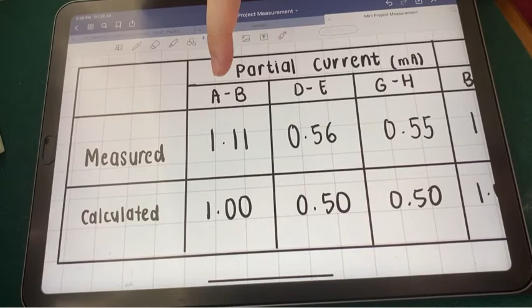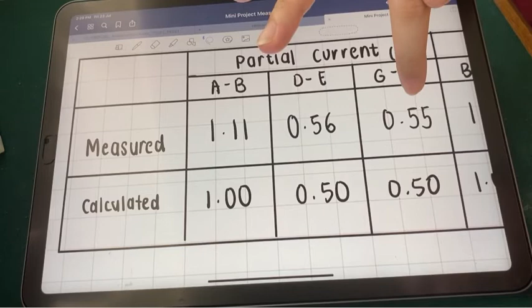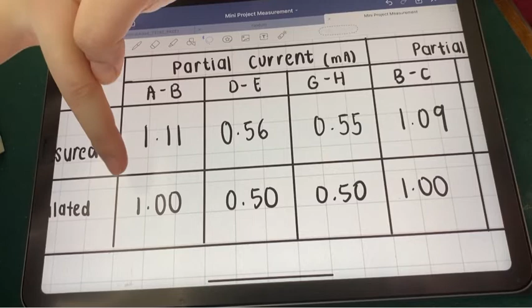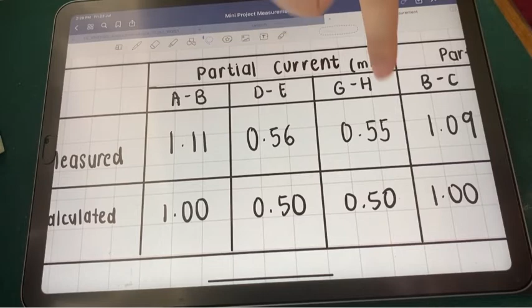At partial current, when measured from the test point, A to B, D, E, and G, H, which I refer to as I1, I2, and I3, we measured 1.11, 0.56, and 0.55. Well, it is calculated as 1 milliampere, 0.5 milliampere, and 0.50.